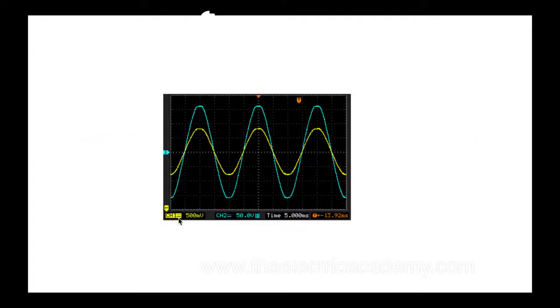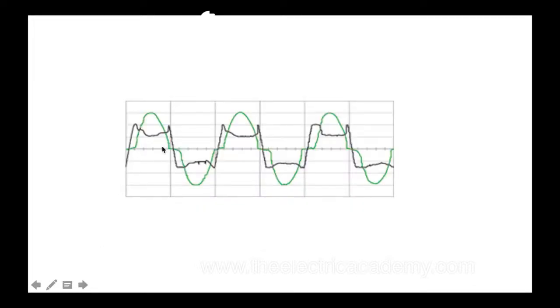Now let's talk about how these breakers work. In an ideal situation, you've got the voltage waveform and the current waveform — they look pretty good, on top of each other. This is a completely resistive circuit because they're crossing the x-axis at the same time; that's what we want to see. What an arc fault looks like: when something goes into an arc fault, you notice that shoulders develop on the current wave at the x-axis or the zero point. The current itself is actually a little lower than the ideal current, which is interesting.